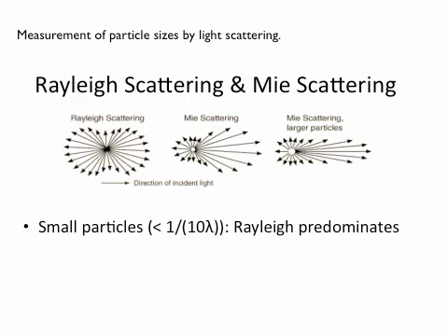The problem starts when your particle becomes larger. The first deviation is actually not on here. If you see this as a peanut, your peanut will start to get distorted. The first distortion would be the Mie scattering, and then if the particle is even larger, you get more Mie scattering. What you'll see is that even the symmetry of this peanut changes: you squeeze it a little bit in the middle and the other blob becomes bigger. For even larger particles, you get a completely different scattering profile, which means that you have to know what the shape of your particle is and how large it is in order to correlate your scattering profile to an actual size. And that's not always easy.